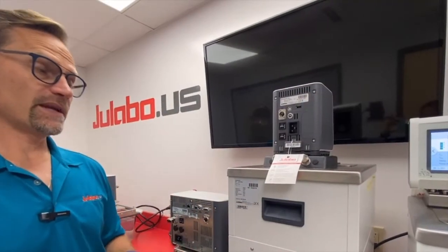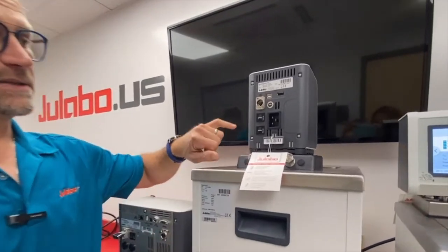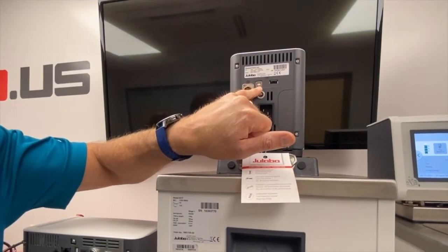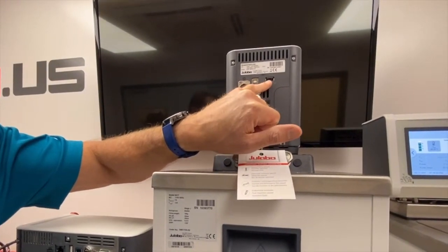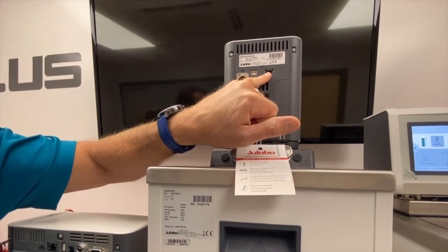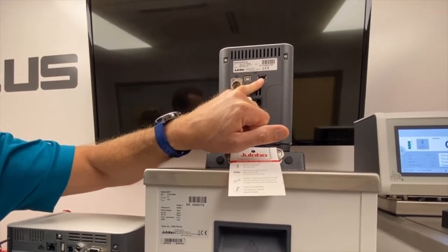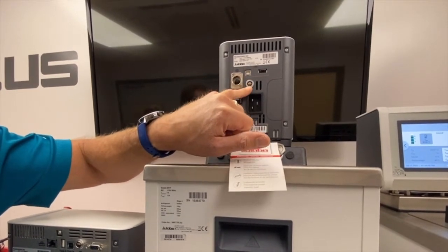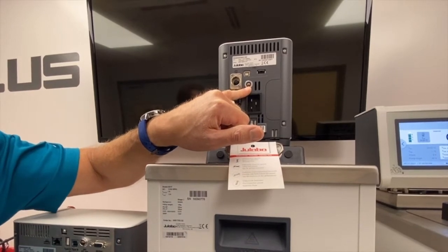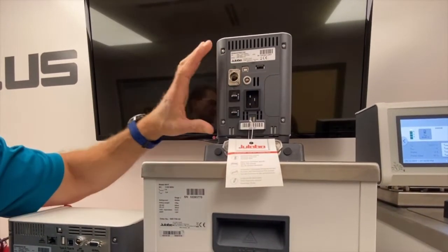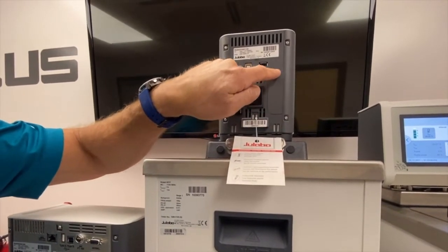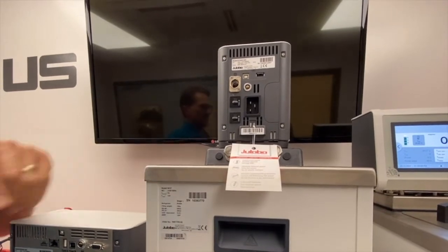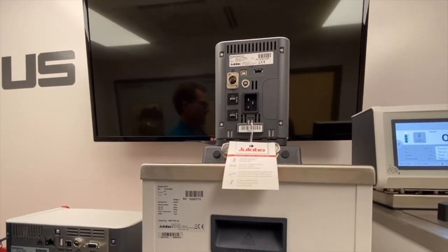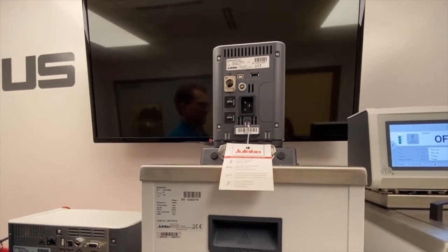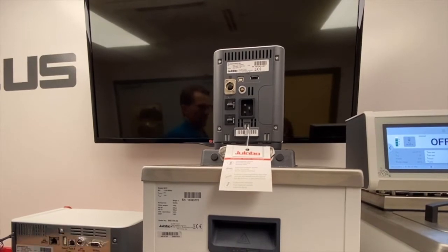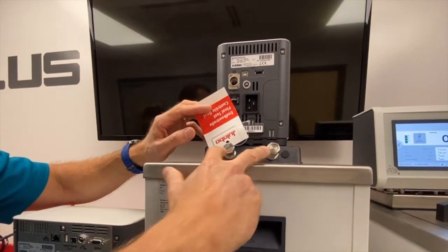So now we'd like to illustrate what's on the back side of the DYNEO DD. Okay, so you have a USB-B port. This is for external communication via USB. We have a USB-A port, which is used for data logging, saving programs, and capturing service information to send for remote diagnosis. We also have the external PT100 port so you can control from an external temperature sensor. And then this is the standard layout for the DYNEO. But in this little cutout here, you can see you can also equip the DYNEO with either an RS-232 serial port or an analog port. If you have a PLC, then you want to control externally by voltage or current. The pump connections for the DYNEO are M16 male.